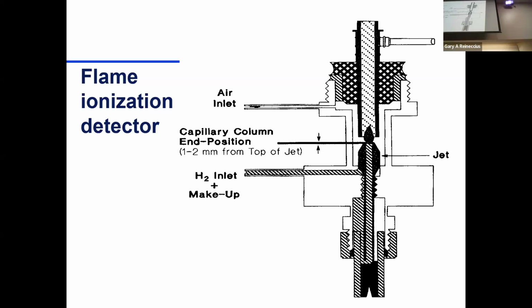The more compound, the more ions, obviously. And right above that is supposed to be a flame up there. It kind of looks like it, doesn't it? A candle, anyway. So there's the jet and the flame. That flame tends to give off ions, ions that are formed in the flame. And that tube it's running up is basically measuring how many ions are formed. So you're measuring what ions are formed as these compounds are burned.